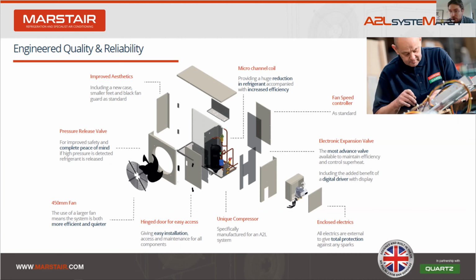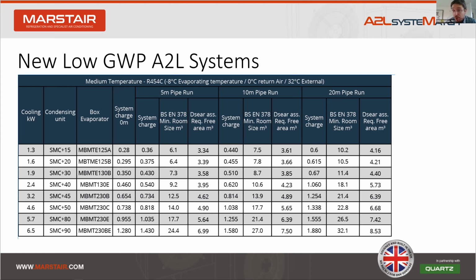So here we go. This is the table I've been building up to. This shows the very low refrigerant charge levels required for our new critically charged A2L system match products. It also shows how easy it will be to select an A2L system match, and you know that you will be within the regulations for refrigerant charge. For example, on the third line down, this is a 1.9 kilowatt system, and at a 10-meter run, this needs just 510 grams. That means it's suitable for a room as small as 8.7 cubic meters.